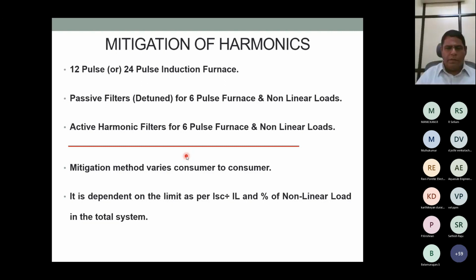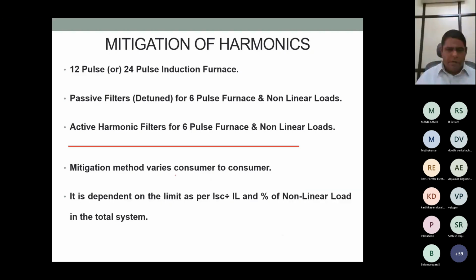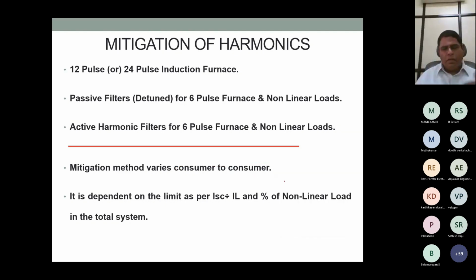This is the second method. Third method is active harmonic filter for 6-pulse furnaces. All three will work, but the mitigation method varies from consumer to consumer. This is what I would like to tell. It is because the consumer location point is totally different, every consumer will have a different limit.